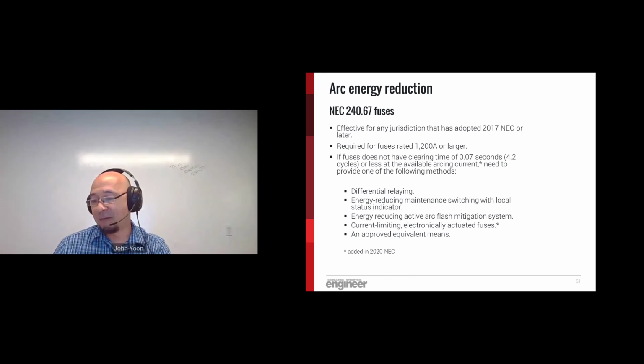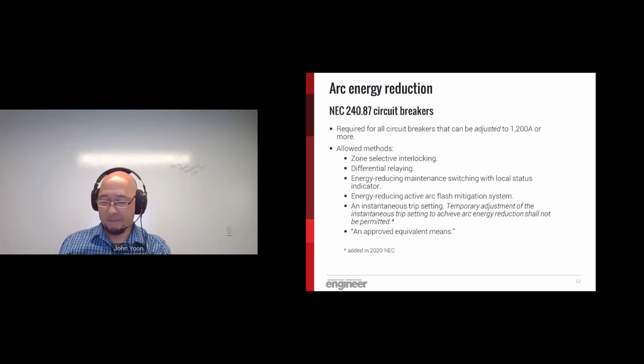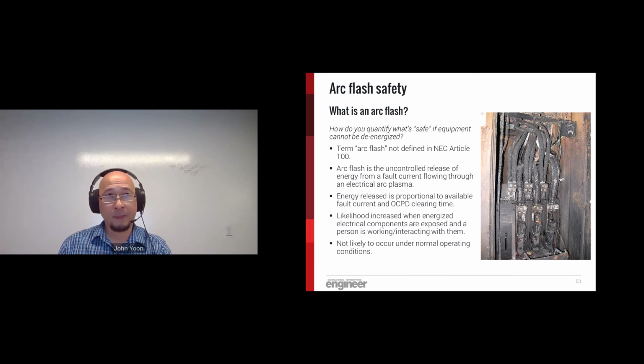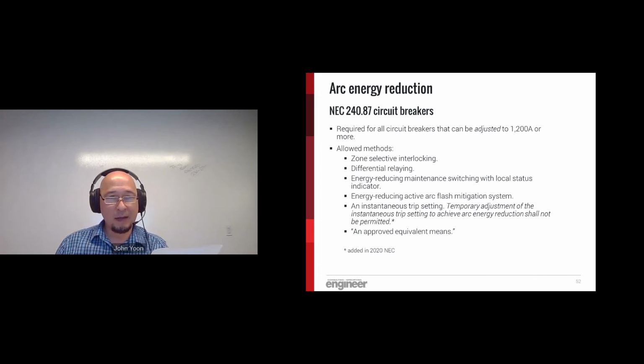The code gives you 5 options here to accomplish this, but unfortunately, with most of these 5 methods, you're basically duplicating functionality that is much easier to accomplish with circuit breakers. We'll see in the next slide that most of these methods are duplicated for circuit breakers. So with the exception of zone selective interlocking and instantaneous trip settings, you can see that the methods clearly mirror those for fuses. I could spend a whole bunch of time on this slide, so we'll probably answer a couple of questions about these later on in the Q&A section. Going back to the previous slide for one quick second, there is one typo in this slide. There is one additional method, which is having an adjustable instantaneous trip setting that meets the requirement.